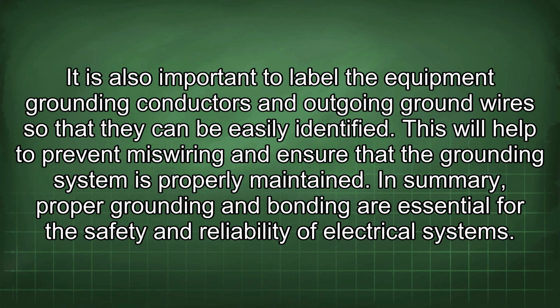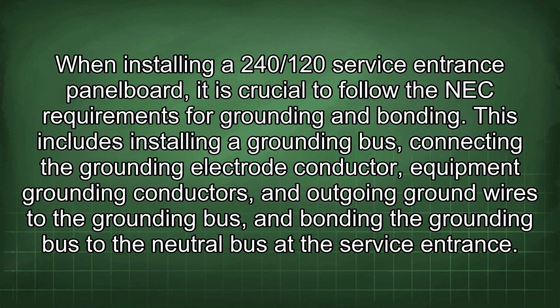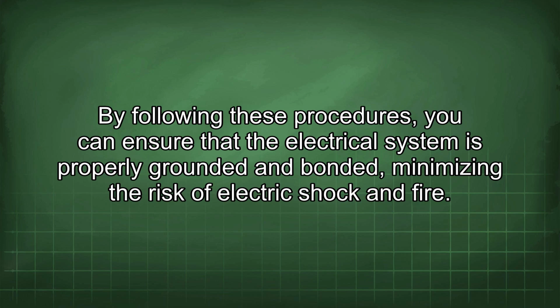In summary, proper grounding and bonding are essential for the safety and reliability of electrical systems. When installing a 240/120 service entrance panel board, it is crucial to follow the NEC requirements for grounding and bonding. This includes installing a grounding bus, connecting the grounding electrode conductor, equipment grounding conductors, and outgoing ground wires to the grounding bus, and bonding the grounding bus to the neutral bus at the service entrance. By following these procedures, you can ensure that the electrical system is properly grounded and bonded, minimizing the risk of electric shock and fire.